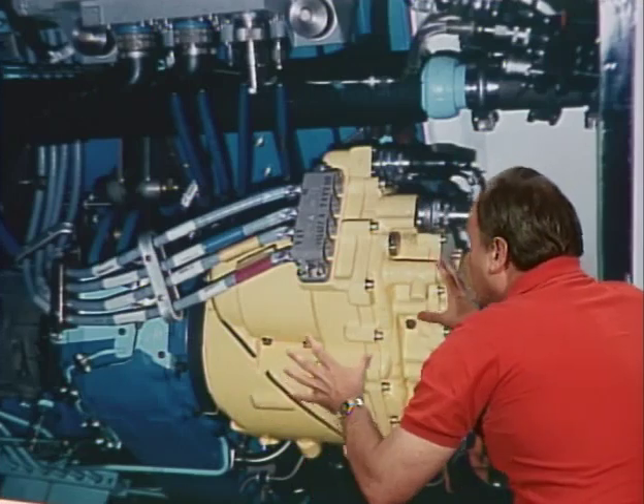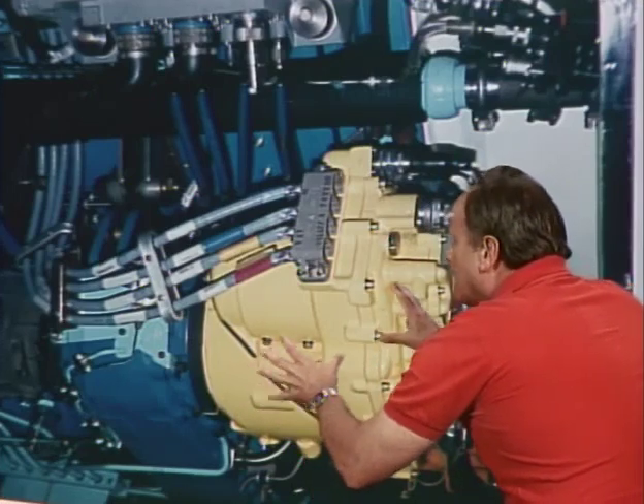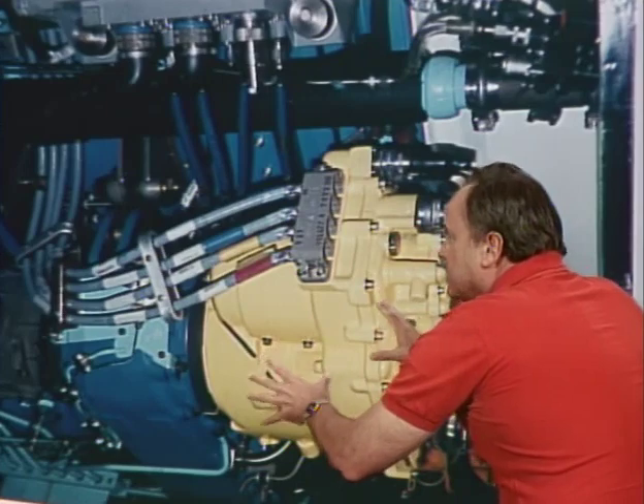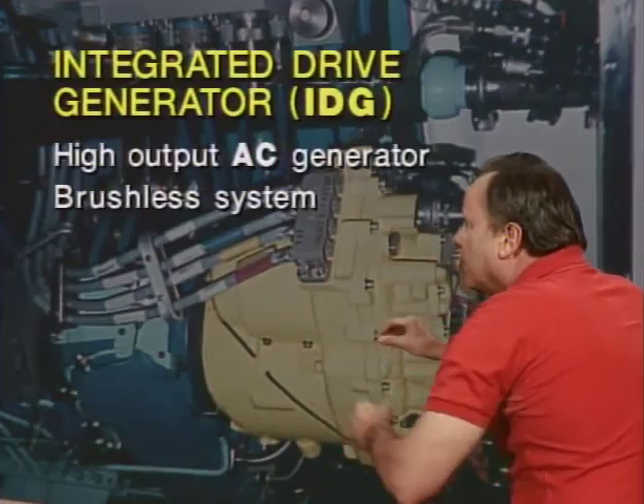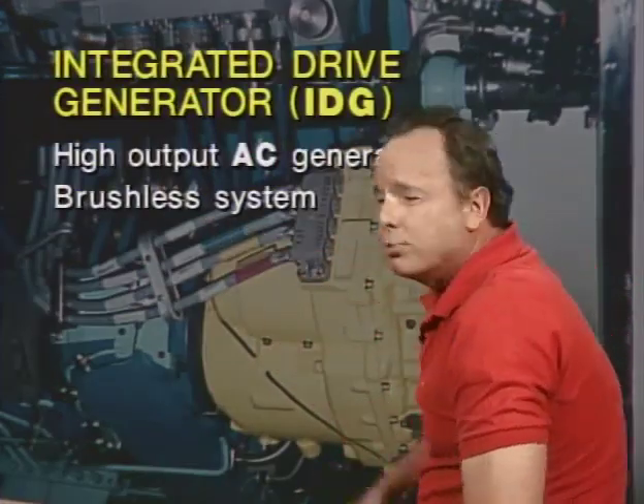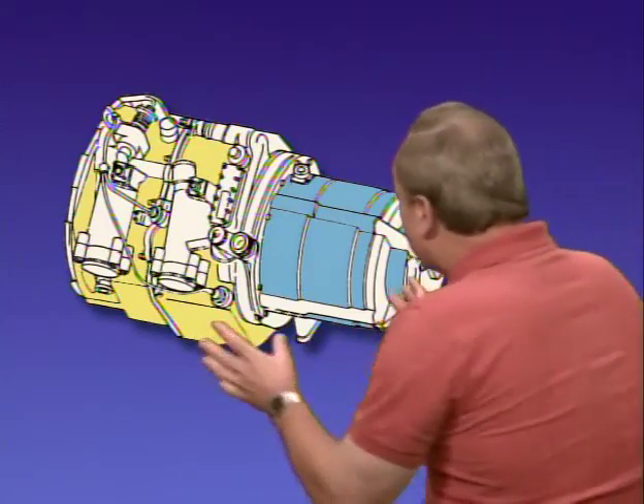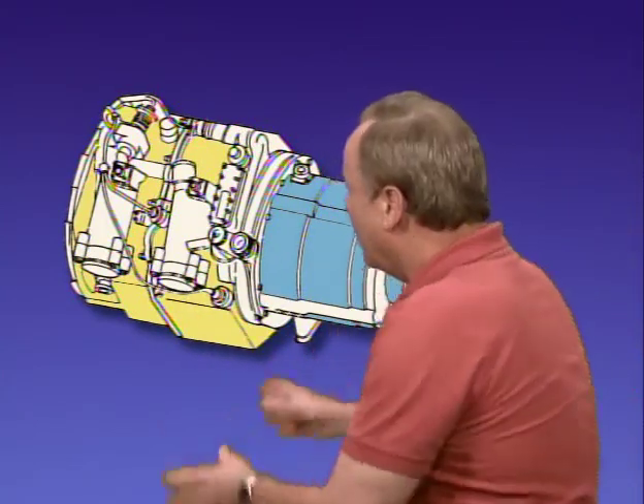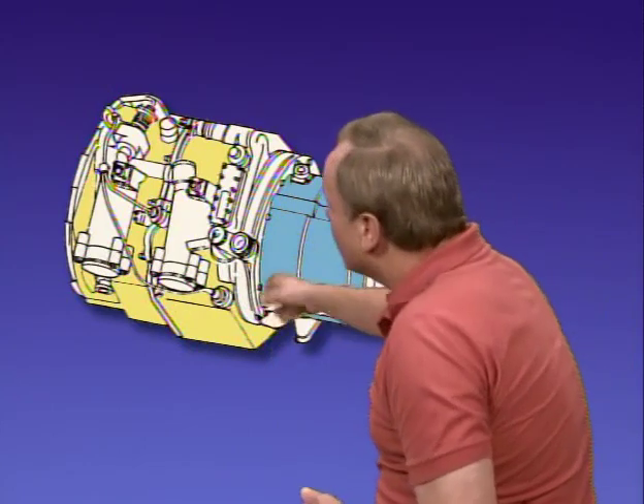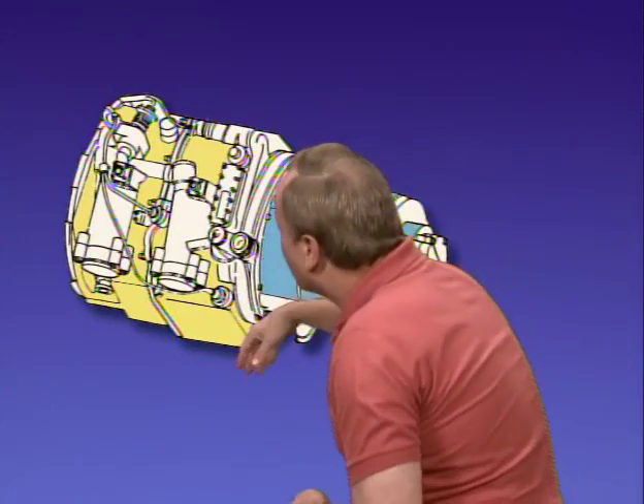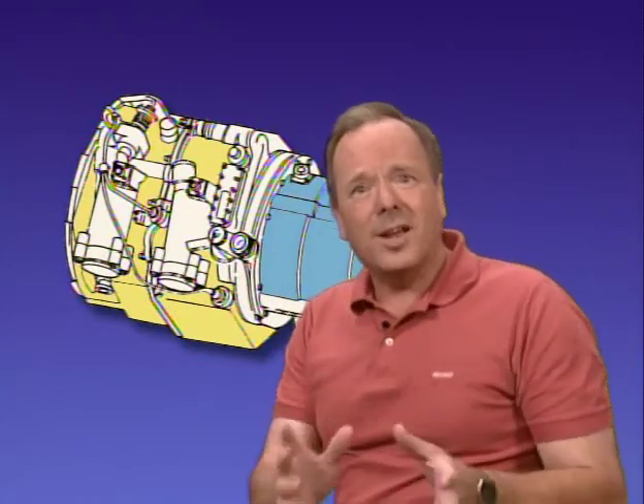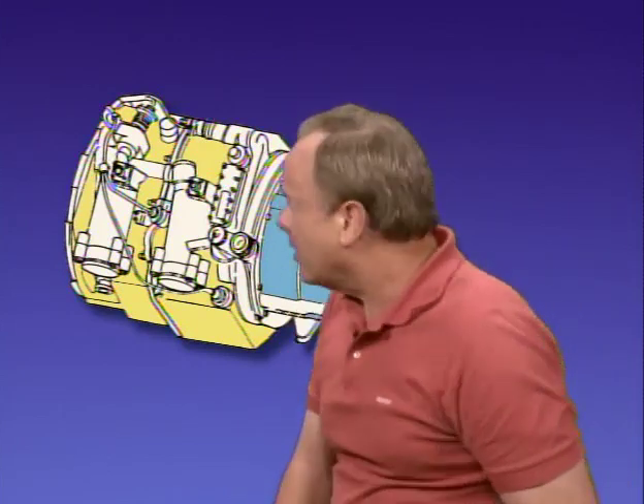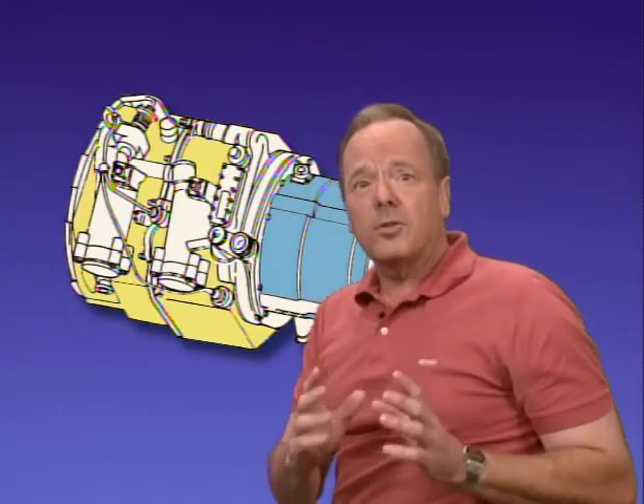Right here is the whole thing, very simple. It's an integrated drive generator, and it employs a high output AC generator and a brushless system to produce current very elegantly and very lightweight. Now here's another look at that neat little package that an IDG is. And in here there's an oil filter, because there's a lot of turning and twisting going on in there, so it's a good idea to have an oil filter. You should check that oil filter every now and then and check it for contamination.